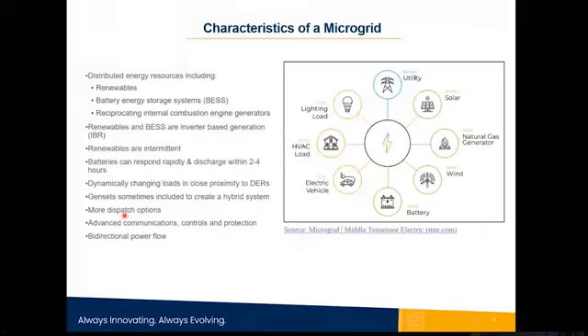Another objective could be environmental emissions. Another one could be power system stability. So depending on the objective function of the microgrid, the dispatch priority can change. And oftentimes smart controls are needed to do that because those dispatch priorities can be changed on the fly during operation. And in order to facilitate that, we need advanced communications. For example, Modbus and different Modbus protocols, and advanced protocols like IEC 61850 and DNP3. So these advanced communications, advanced controls, a microgrid controller sometimes is a purpose-built microgrid controller. At other times, it may be just a master PLC controlling the entire system.